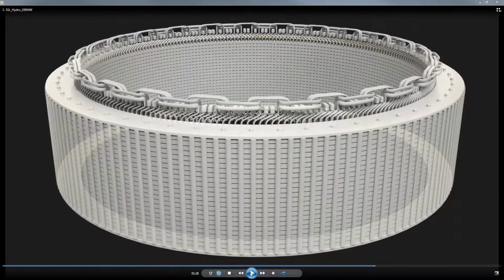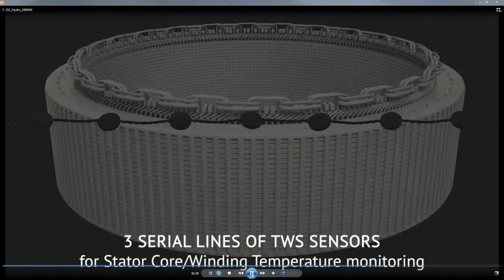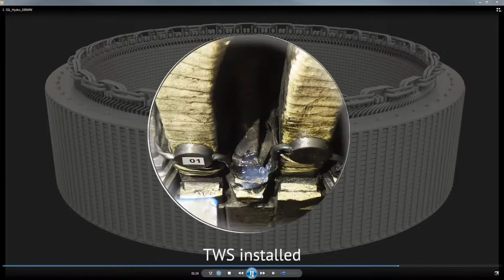And we also install some on the pressure plates. The reason for that is the pressure plates, with the compression bolts, are there to make sure that the laminations are stacked correctly and tightly and remain tight. You cannot have laminations that come loose, because if they come loose, they start rubbing against each other, and then the insulation will wear out, and then you'll have some contact between 2 laminations, creating eddy currents, causing overheating, causing all kinds of issues. And historically, this combination of pressure plates and compression bolts is usually neglected. The maintenance is not done on those, and they become loose, and everybody wonders why the core is overheating. Well, in many cases, that's why. So it's important to monitor that and be able to see if those are coming loose.